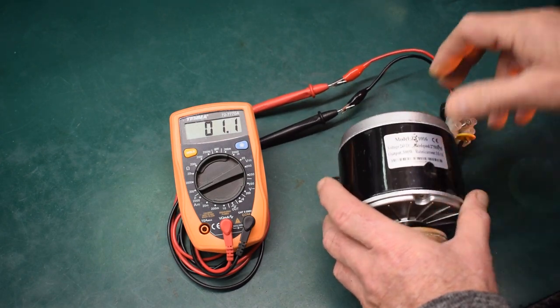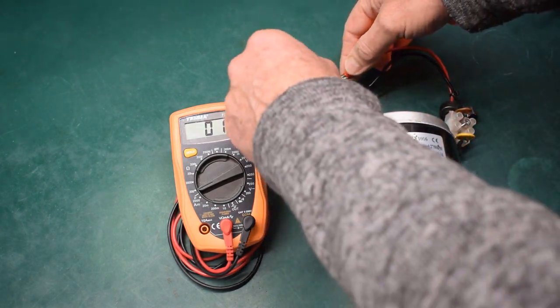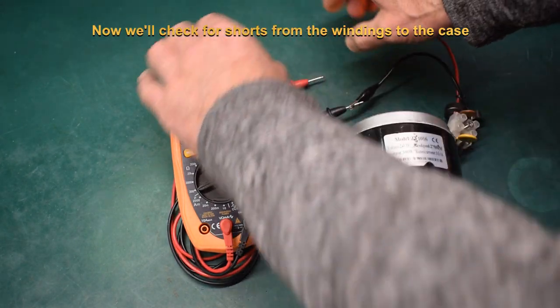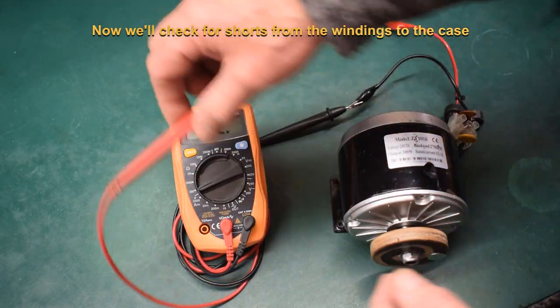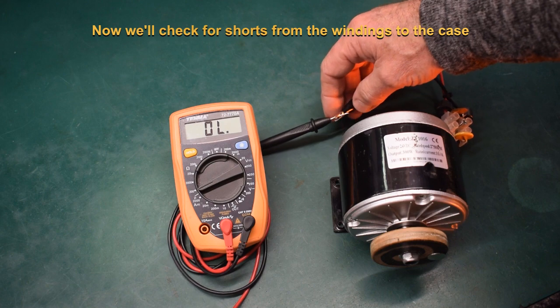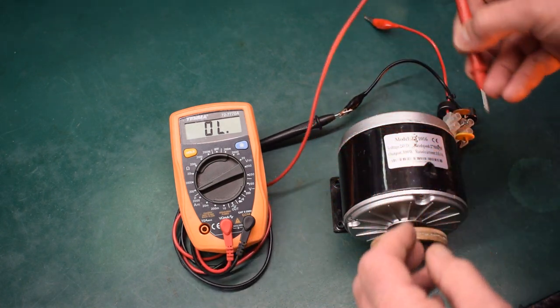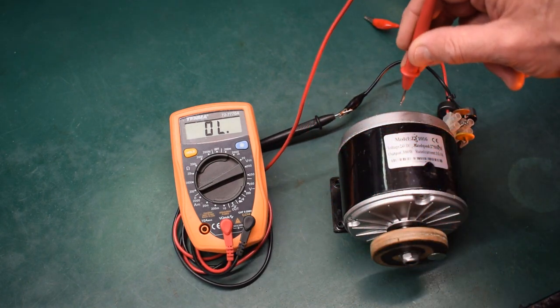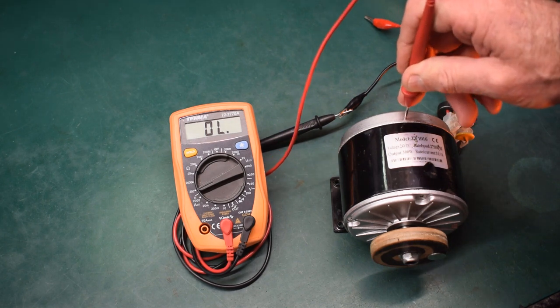The next test to do on the motor is to check for continuity between the windings and the case. We'll leave one leg of the motor connected to one brush on the motor and then we'll place the other probe on the casing of the motor here.